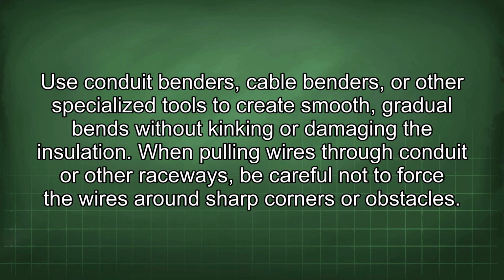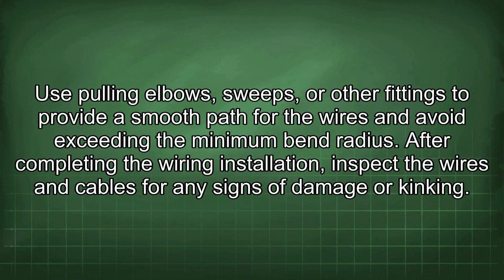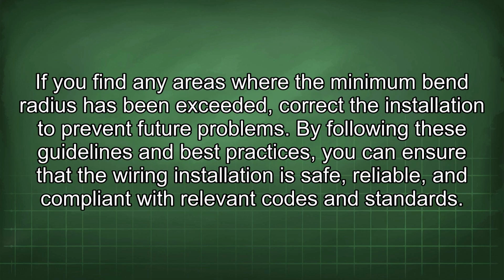When pulling wires through conduit or other raceways, be careful not to force the wires around sharp corners or obstacles. Use pulling elbows, sweeps, or other fittings to provide a smooth path for the wires and avoid exceeding the minimum bend radius. After completing the wiring installation, inspect the wires and cables for any signs of damage or kinking. If you find any areas where the minimum bend radius has been exceeded, correct the installation to prevent future problems.